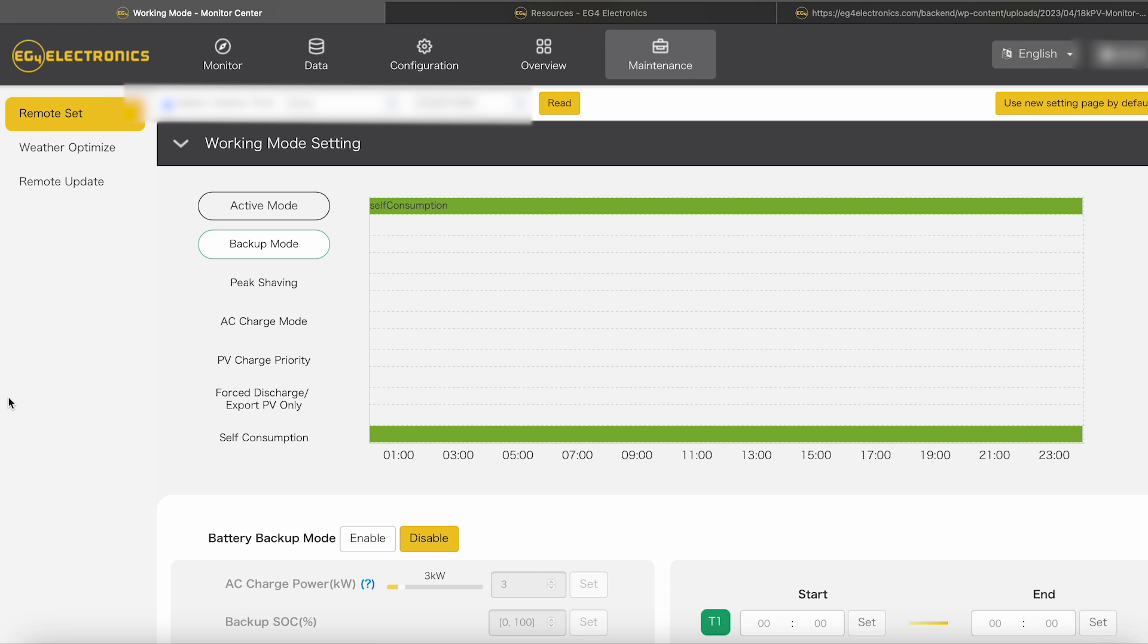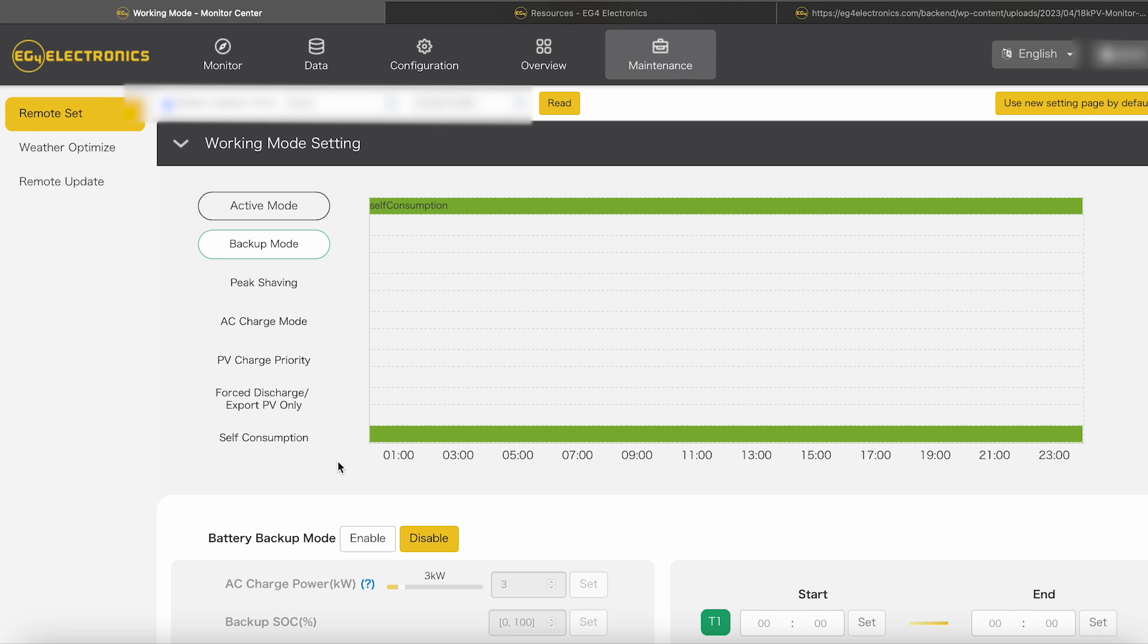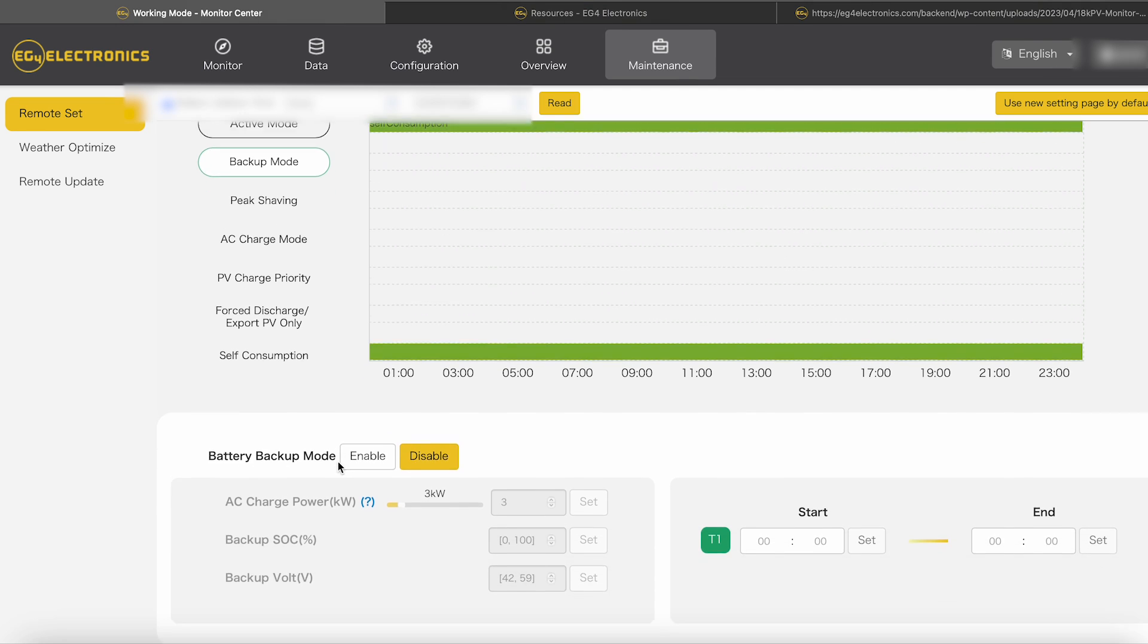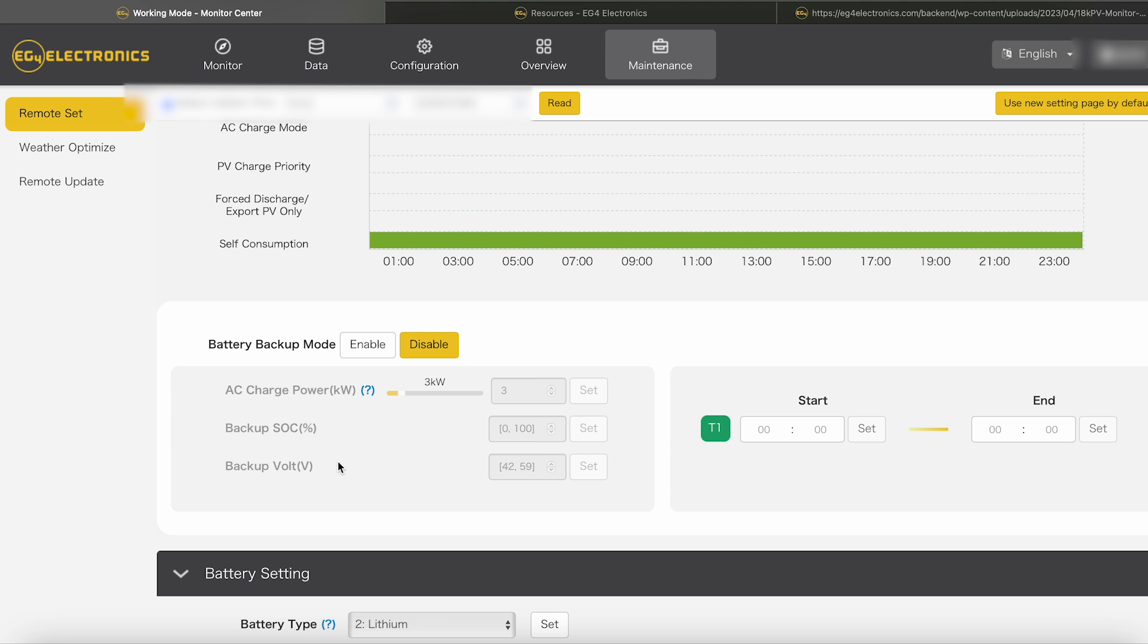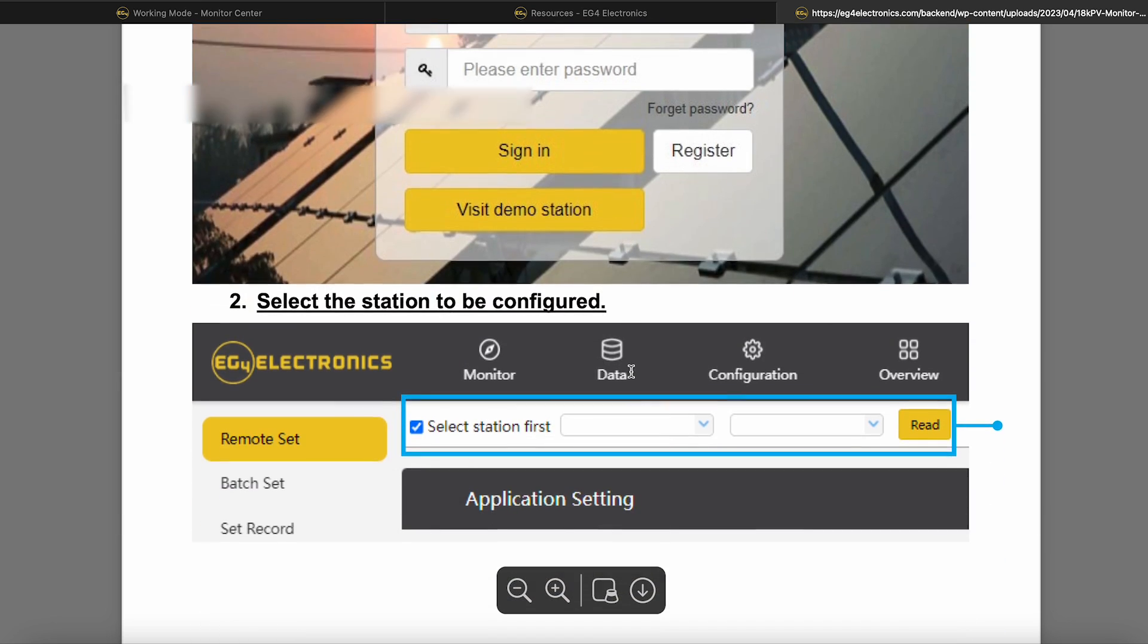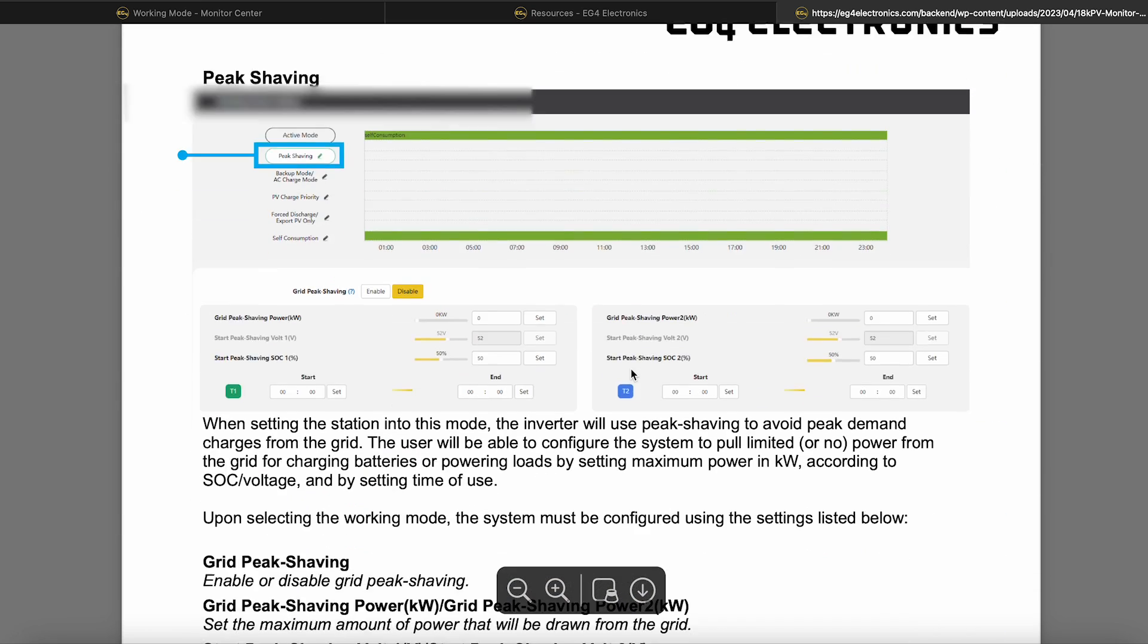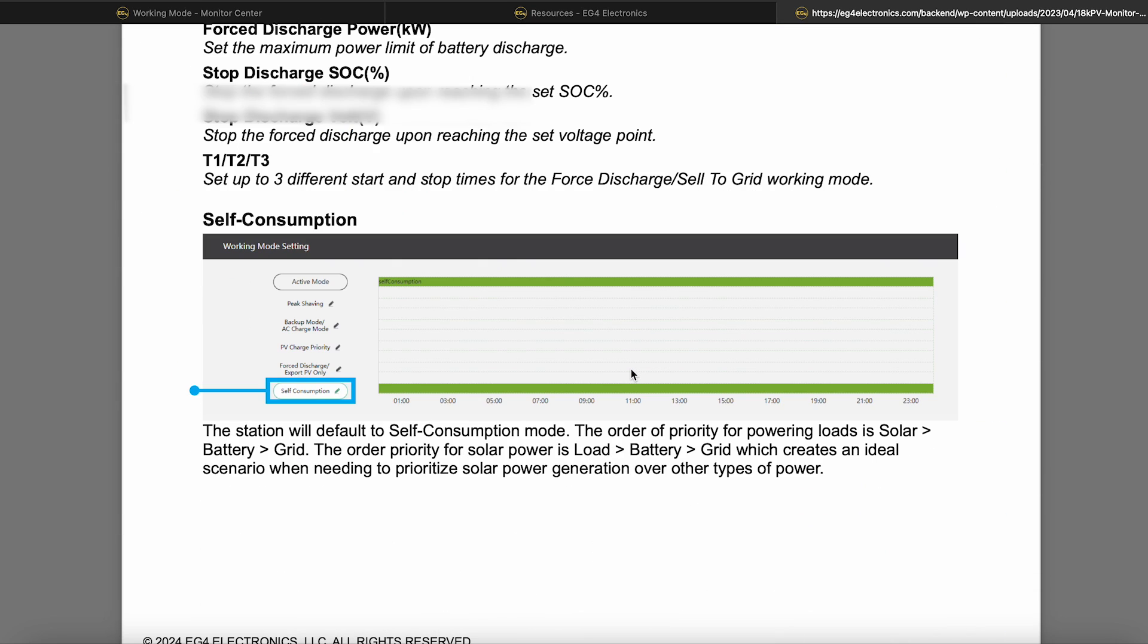Because that's where it's going to be reading what's coming in and what would potentially be going out to keep it from selling back. So that's where I have mine set. I just ran it back into my parents' main grid panel, put on your L1 and L2 in there, and you're going to be good to go. And then we're going to scroll down to working mode. And as you can see, it's saying I'm in self-consumption mode. So you just pick whichever mode you want to be in. I'm in self-consumption because that's the one that's green highlighted at the top. And it's pretty much going to automate everything. So it tries to run everything off of solar when it can.